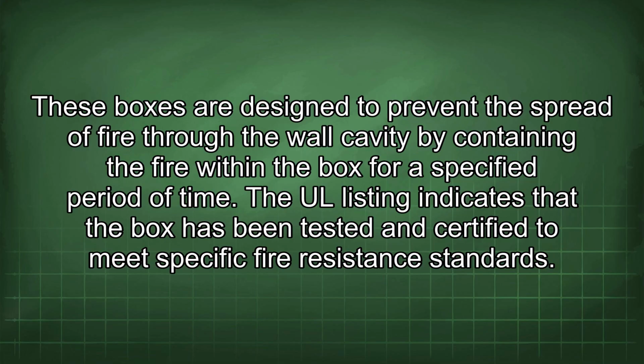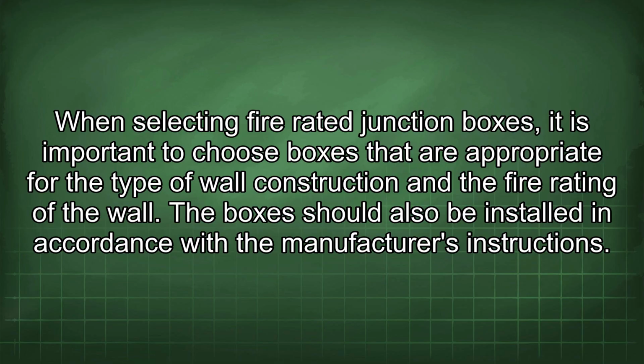The UL listing indicates that the box has been tested and certified to meet specific fire resistance standards. When selecting fire-rated junction boxes, it is important to choose boxes that are appropriate for the type of wall construction and the fire rating of the wall. The boxes should also be installed in accordance with the manufacturer's instructions.